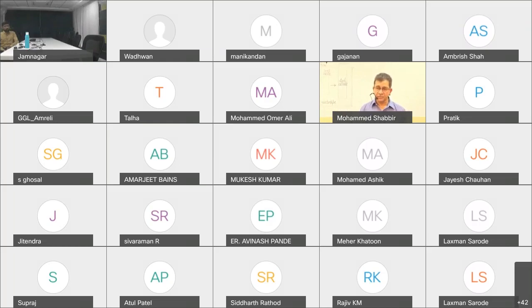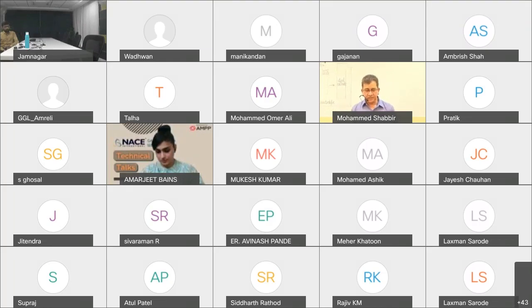Is this for soil application or water application? It's a soil application. Okay, for the soil application, normally the pipeline potential is already fully saturated and stable, so there won't be much difference. If we really want to see what is happening at the different reference electrodes, we can separate this reference electrode circuit from the rectifier, which is operating under manual. So we'll have a small panel showing the performance of the reference electrodes. Accordingly, we can adjust it on site. But in principle, there will not be any issue with any of the reference electrodes.